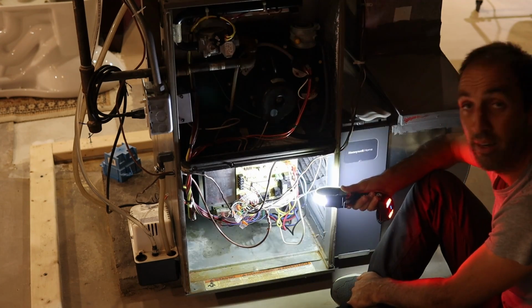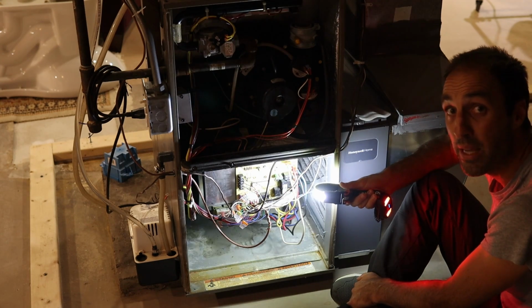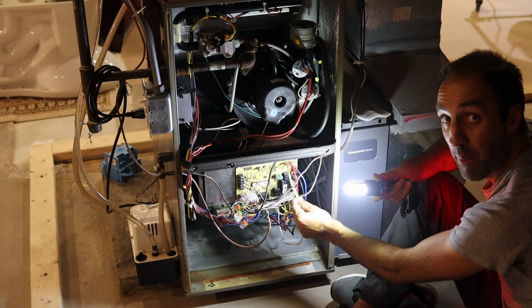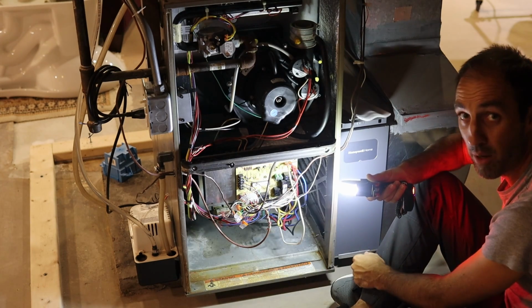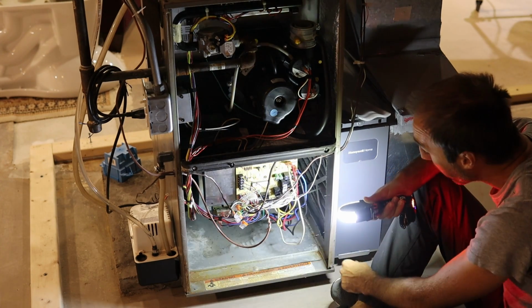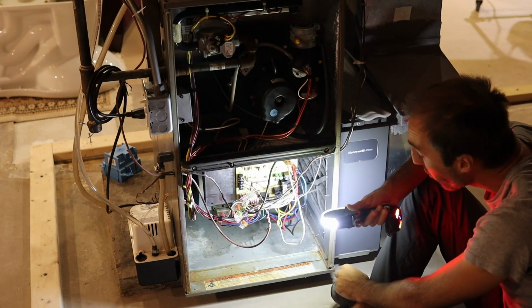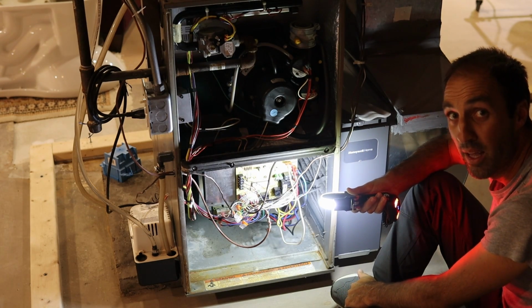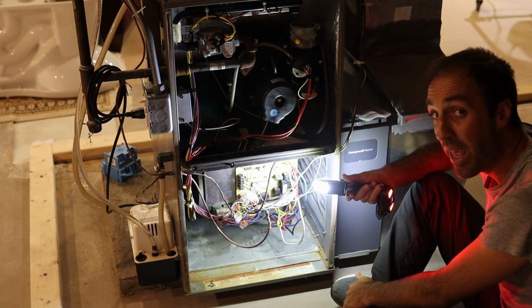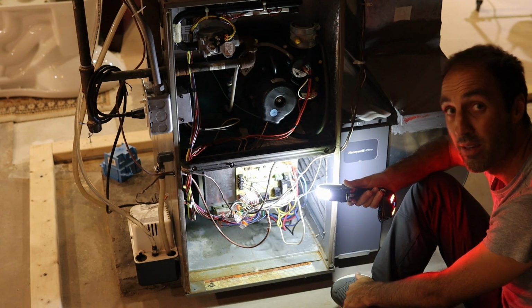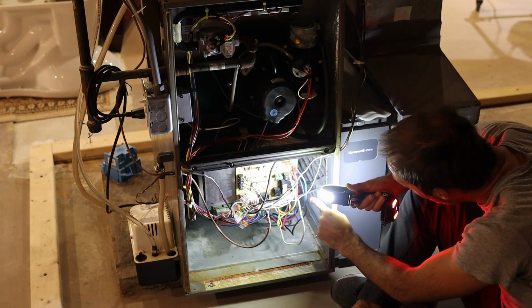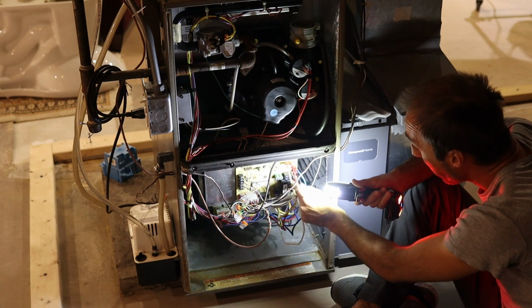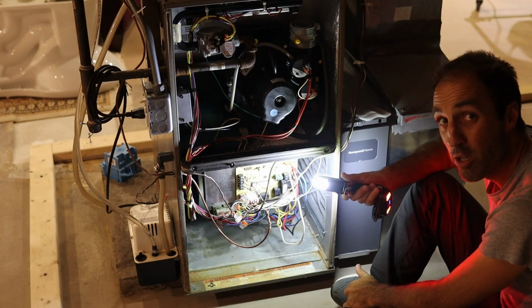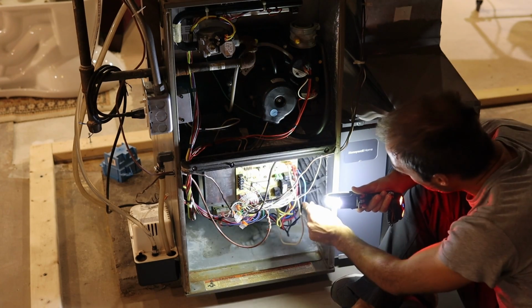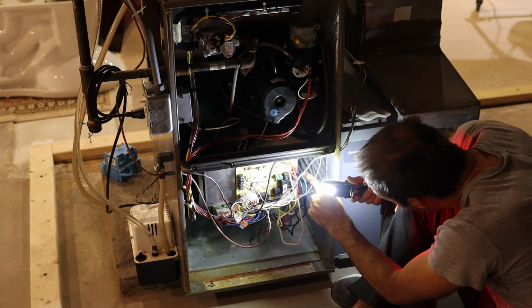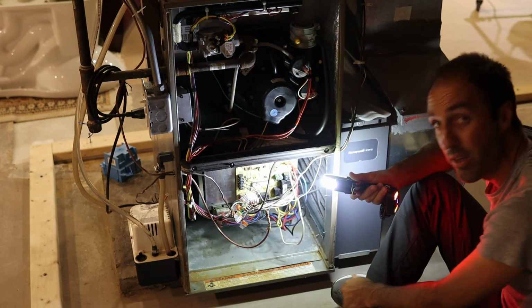Now this fan can run at different speeds. It's got a yellow wire coming off the fan, a red wire, a blue wire, a black wire and a white wire. There's a total of 5 wires coming off this fan. Each of those wires sets the fan to operate at a different speed. Right now on my control board, the yellow and the red ones are in the park positions, which means they're not being used. The blue wire on my system is going to cool, and the black one is going to heat.